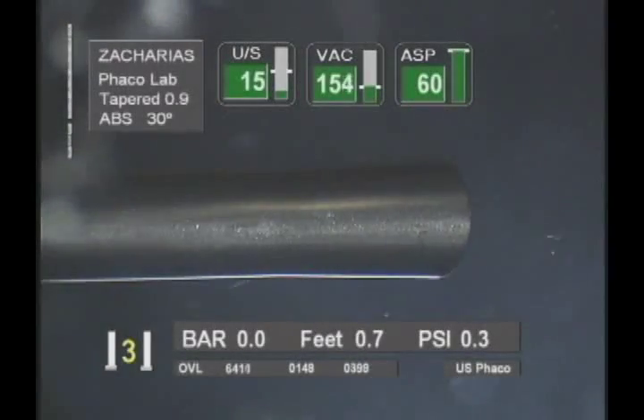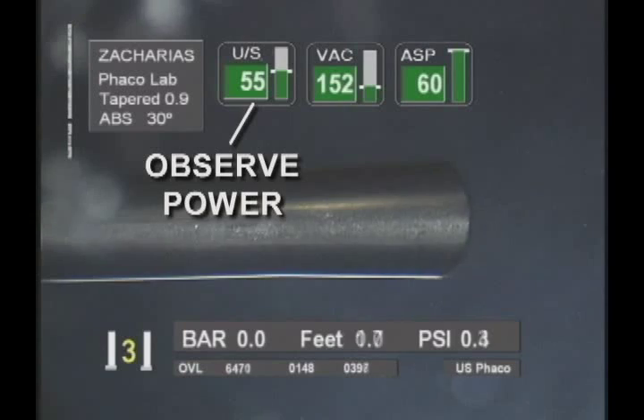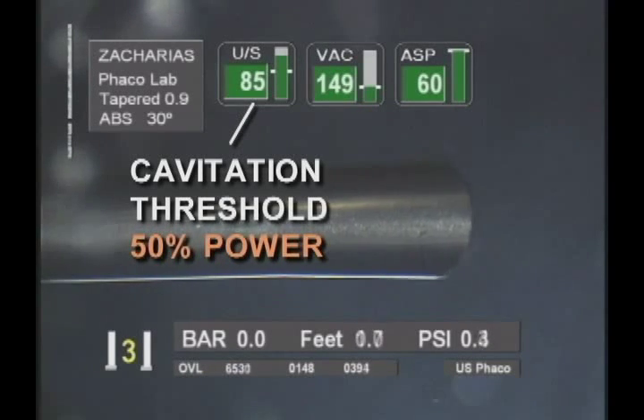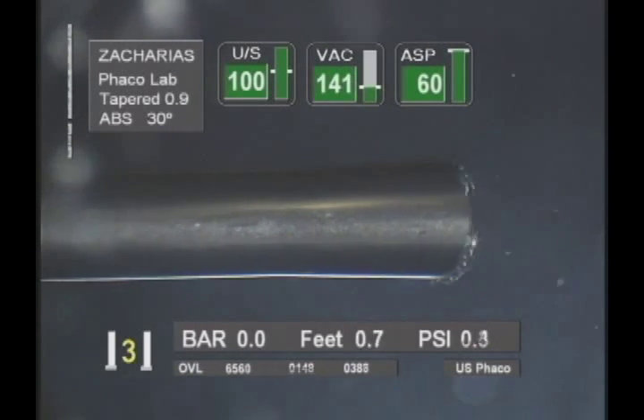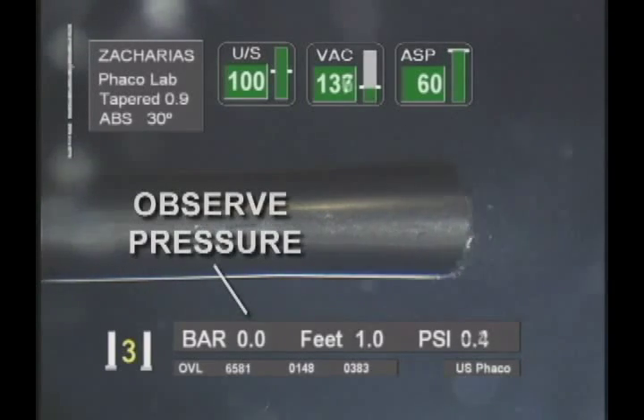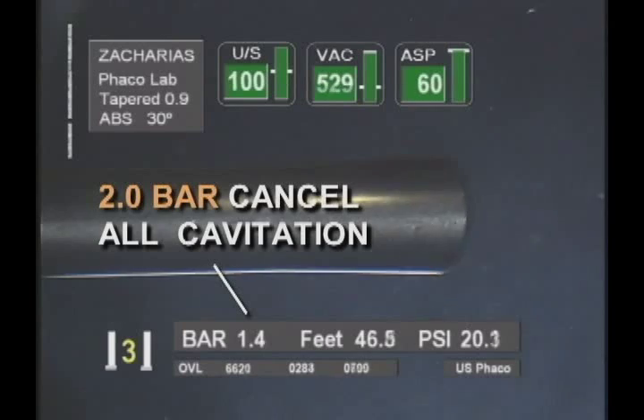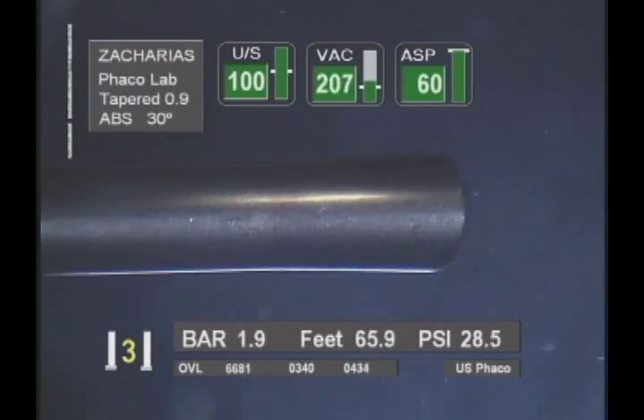Cavitation did not contribute to any increase in cutting efficiency. We have demonstrated that cavitation is present at the tip of phaco probes only when ultrasonic power is high enough, typically above 50% power. Inspired by submarine hydrothermal vents, we used hyperbaric conditions to totally cancel cavitation at the tip of the phaco probe, both when freely exposed to water and in close proximity to solid bodies similar to cataract fragments.